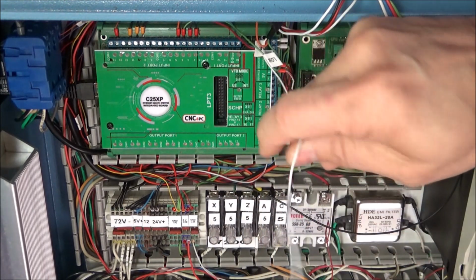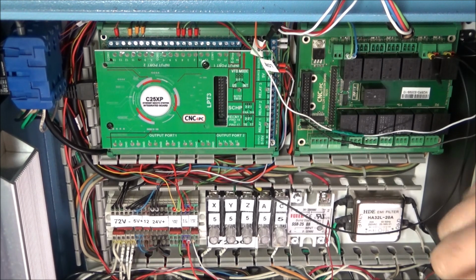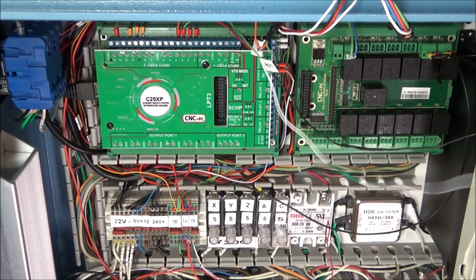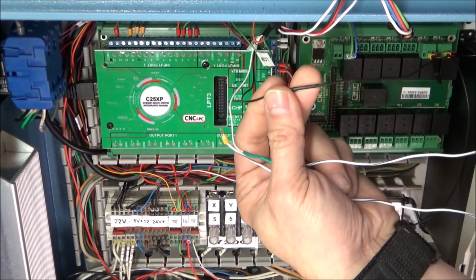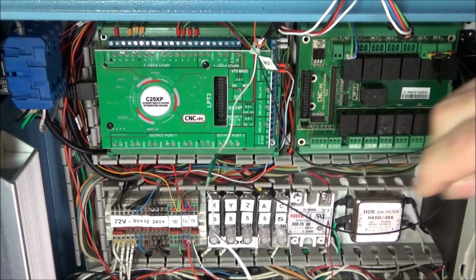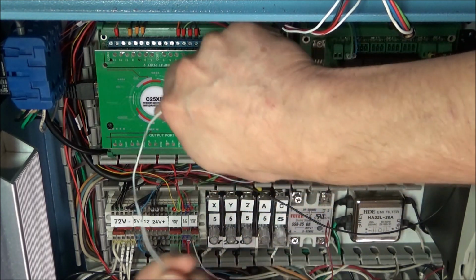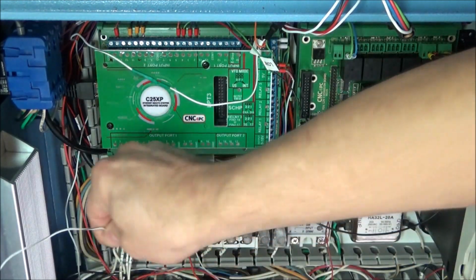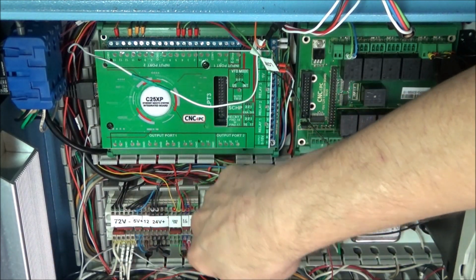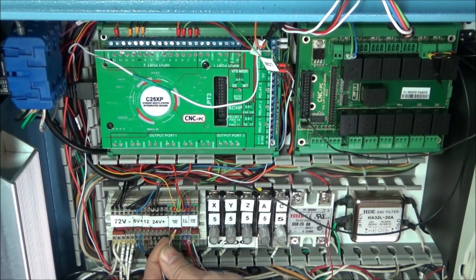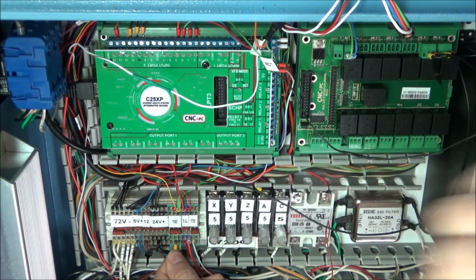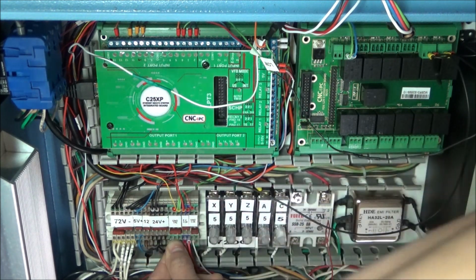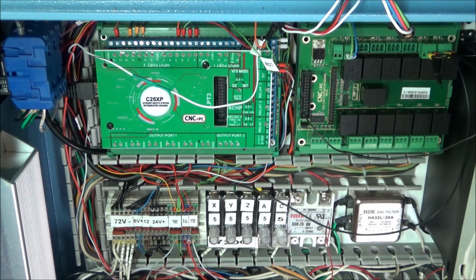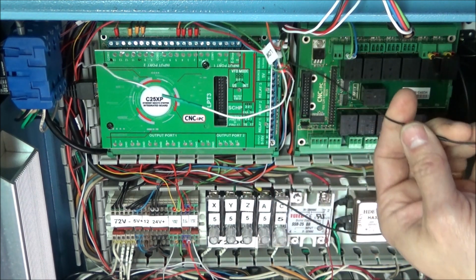And then last is our 24 volt common for the solenoid. So we're sending 24 volts out to the solenoid, and then we have to have a return back to our tri-power power supply or our 24 volt source. So we're going to bring that over, and we're going to put it on here to our tri-power common. All right, so that pretty much takes care of this harness.